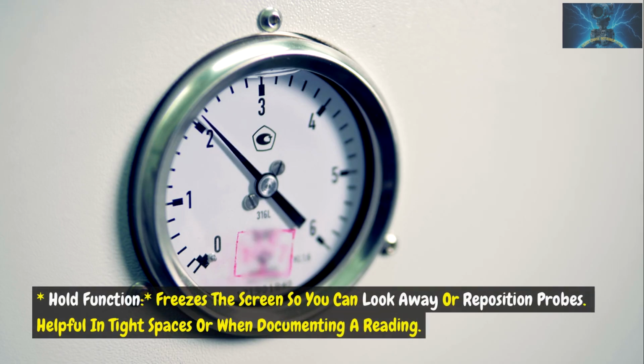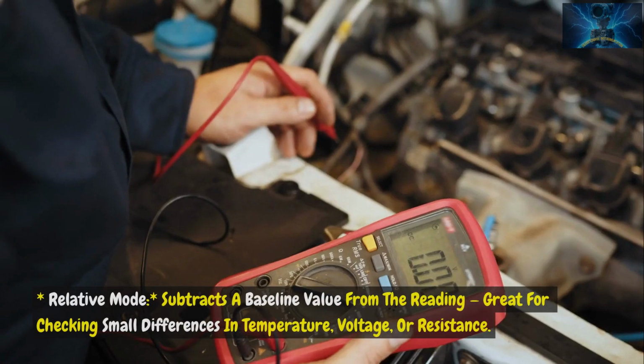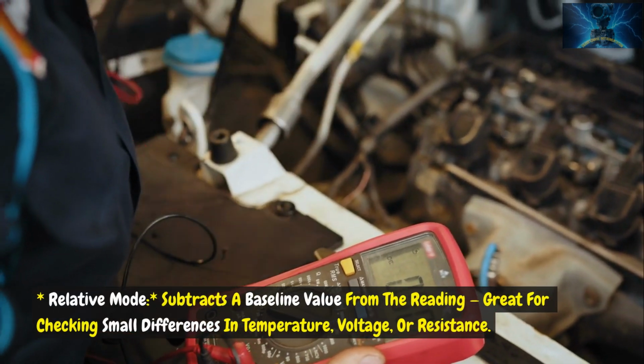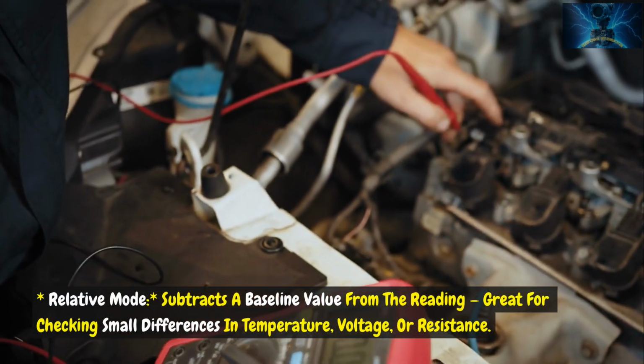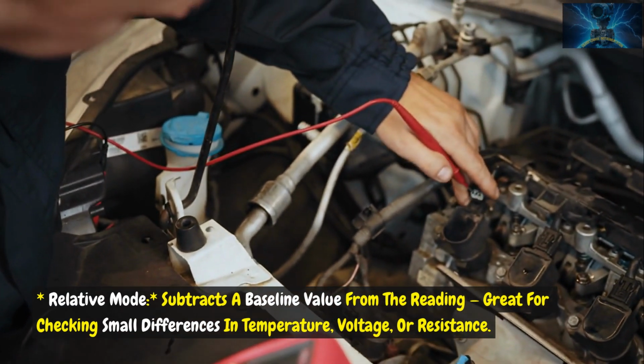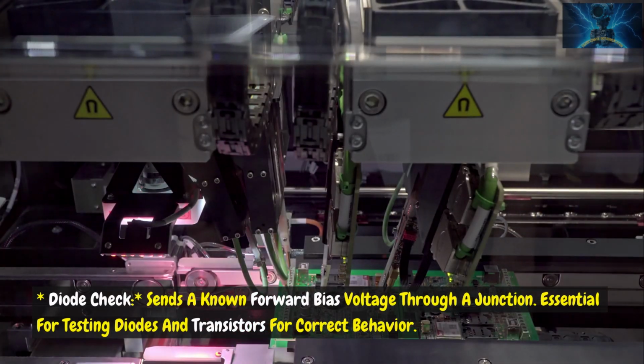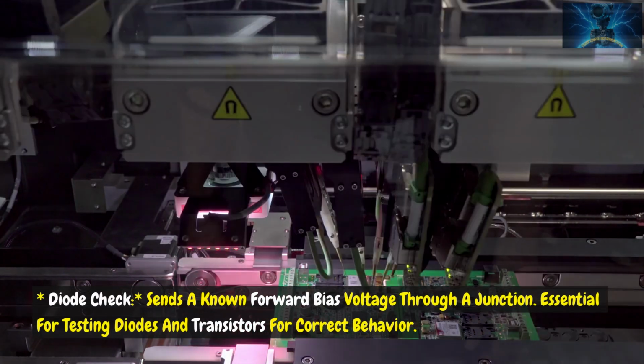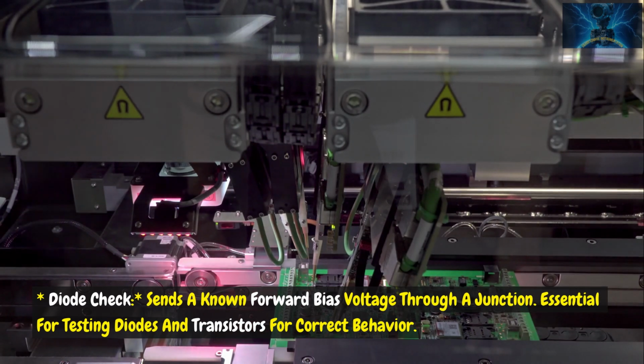Hold Function freezes the screen so you can look away or reposition probes, helpful in tight spaces or when documenting a reading. Relative Mode subtracts a baseline value from the reading, great for checking small differences in temperature, voltage, or resistance.